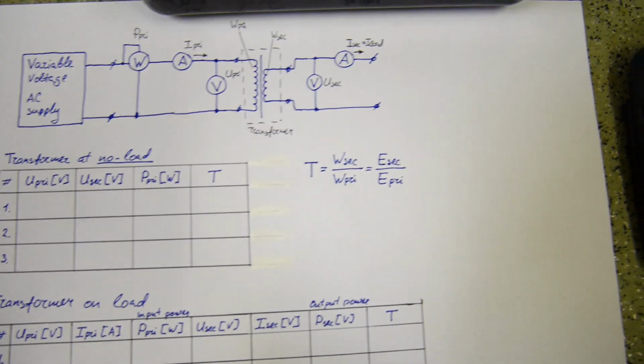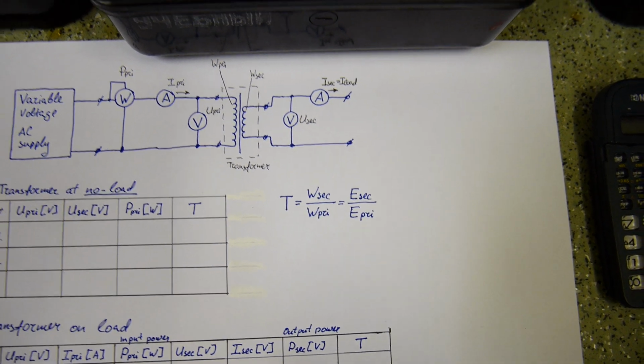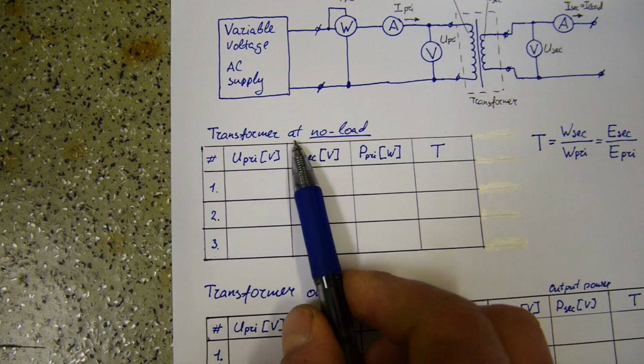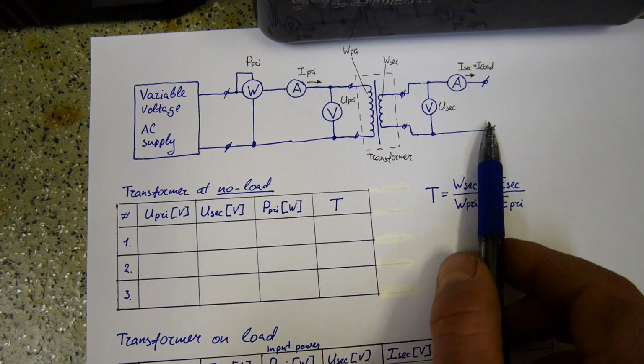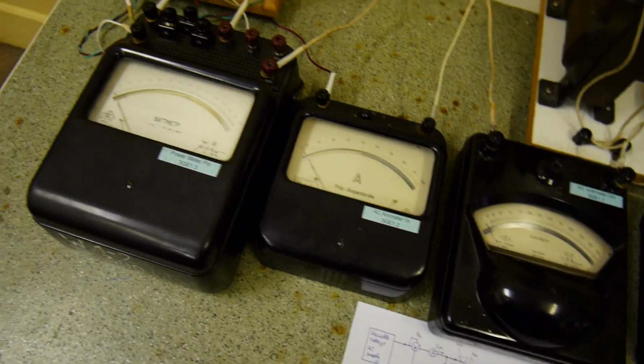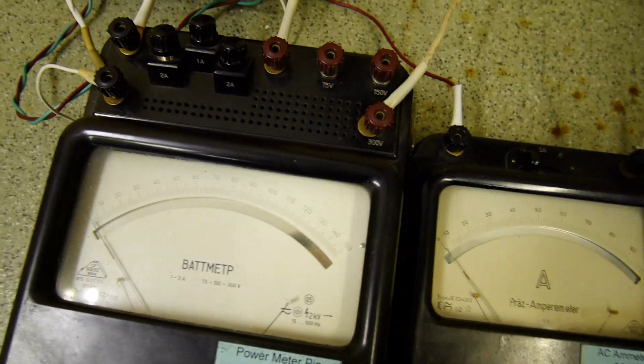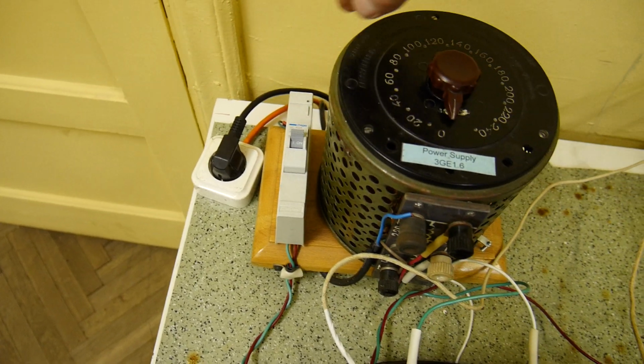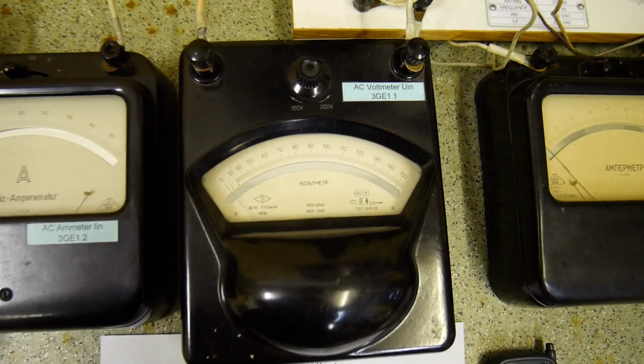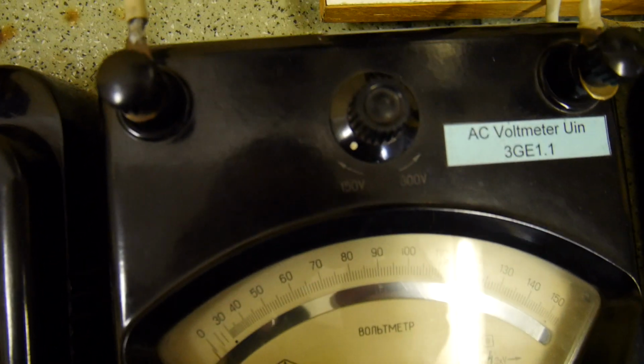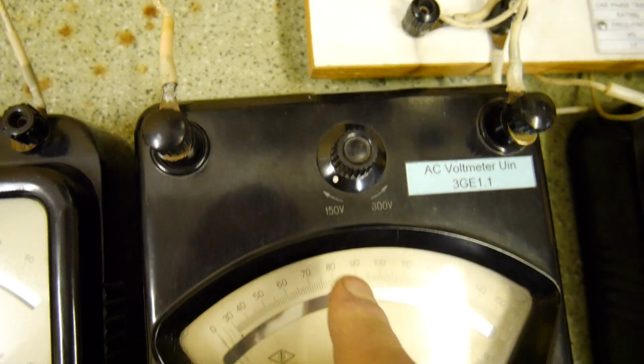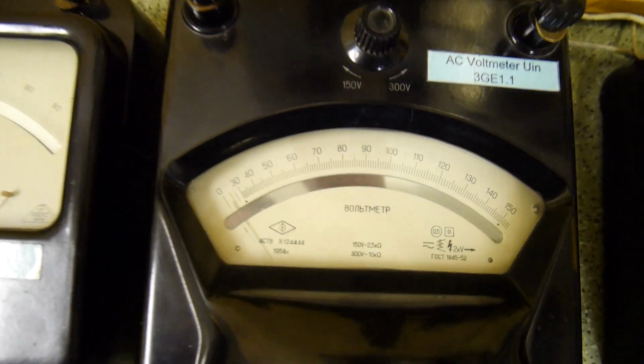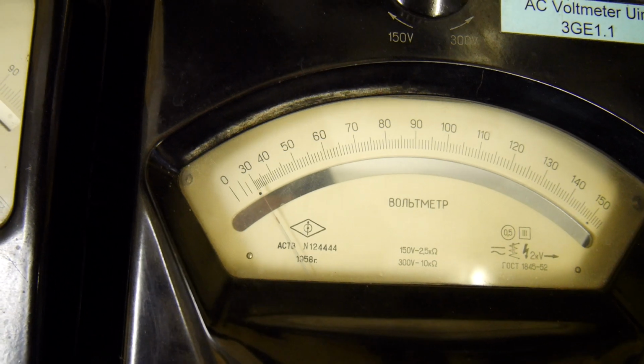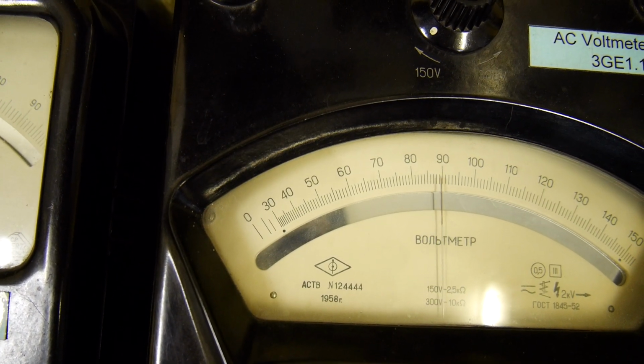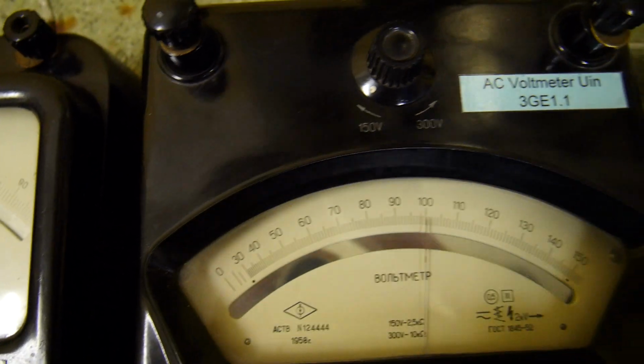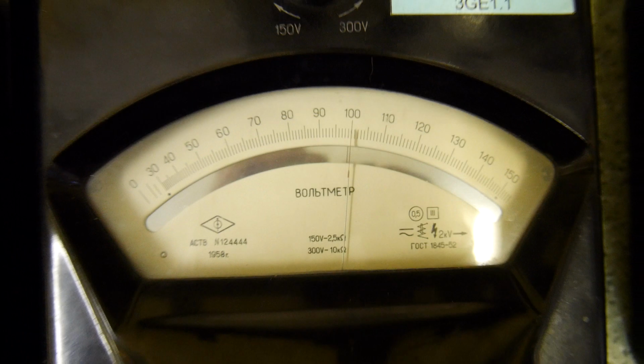So let's check the turn ratio experimentally. To do this, we will operate our transformer at no load. It means that the load is disconnected. So I will apply some voltage to the transformer. At first I will enable power, and now I will apply the voltage to the transformer. The full range of our voltmeter is 150 volts. So I will apply, let's say, 100 volts. Here it is, so we have 100 volts, okay.